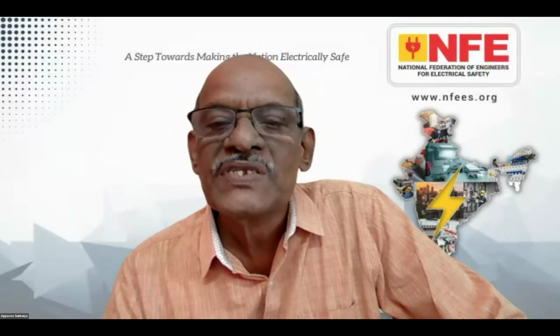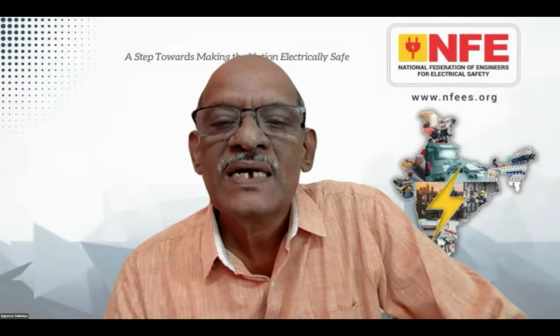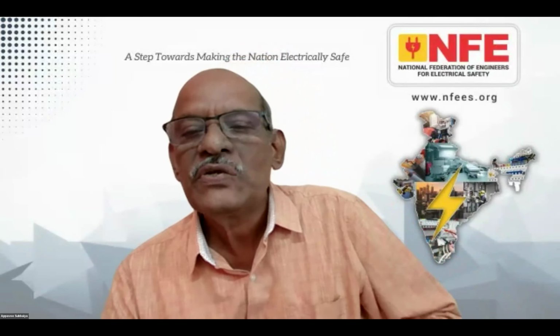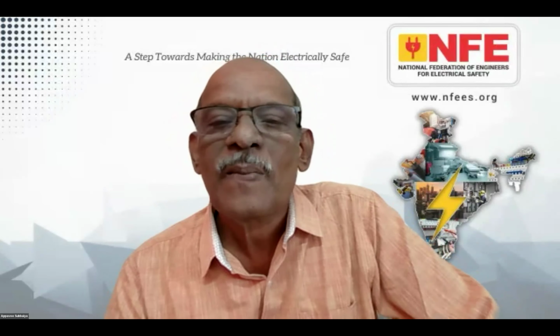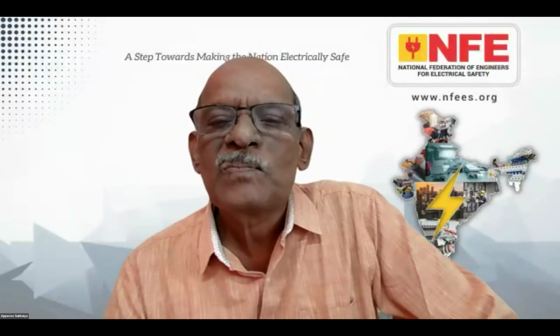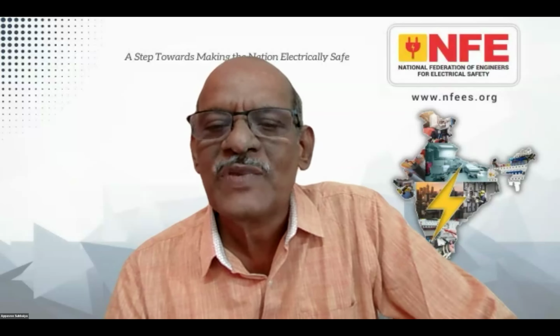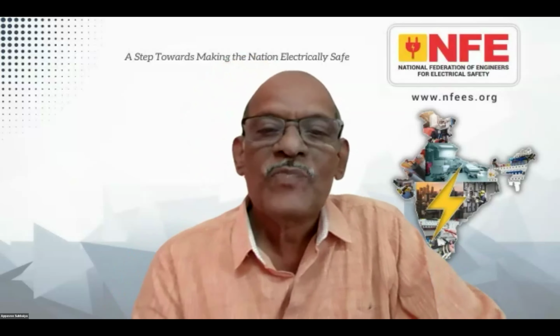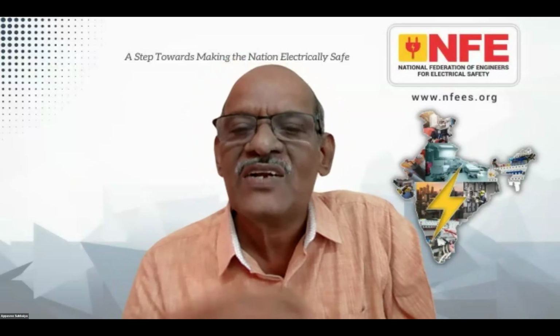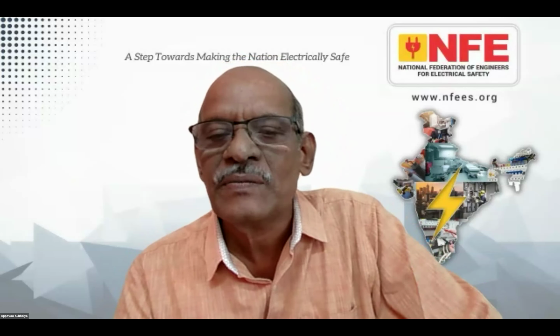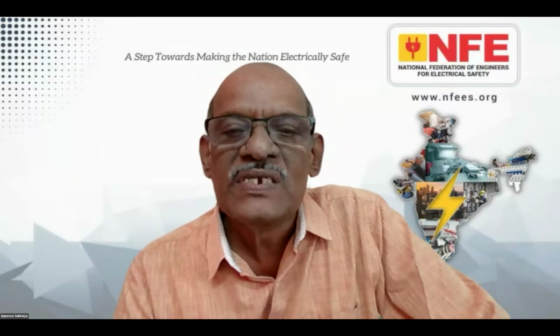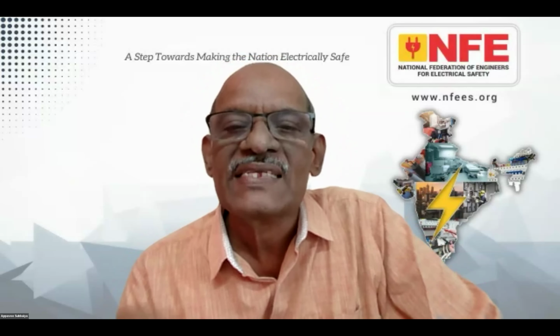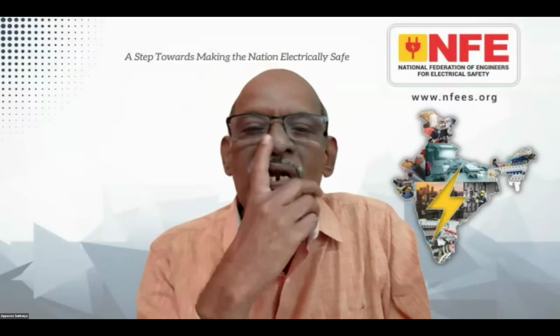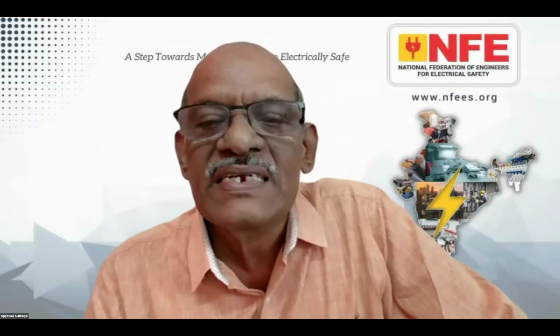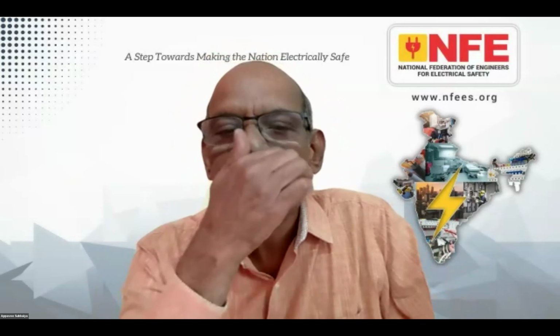all electrocutions are happening due to high impedance fault and no action from utility or public. Yes, all public place accidents are due to high impedance fault. The public can't do anything on this, only the utility can do. And another question is, why the only way, let's say, if it can be avoided with overhead cable, which DISCOM is supplying power?